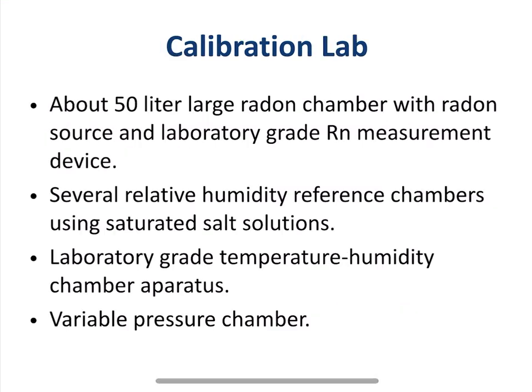About device calibration. A large 50-liter radon chamber with a radon source and a laboratory-grade radon measurement device was used. Several relative humidity reference chambers using saturated salt solutions were prepared. A laboratory-grade temperature and humidity chamber apparatus was employed. The variable pressure chamber was home built.